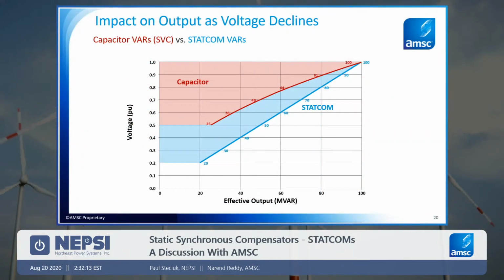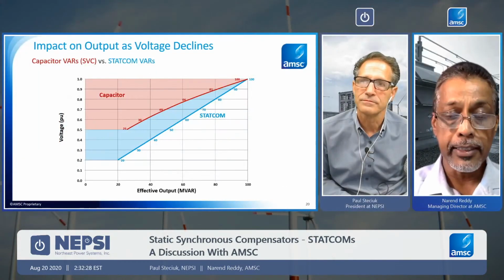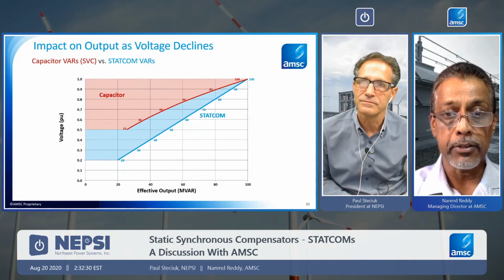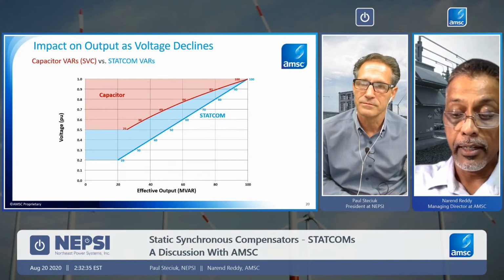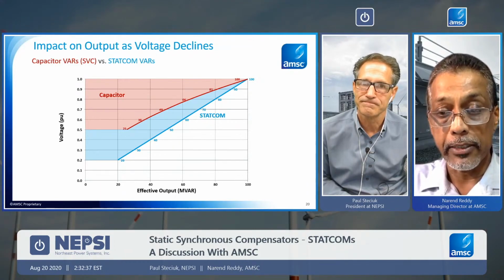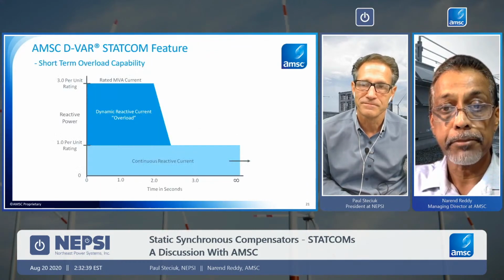What that means is that STATCOM technology can continue to operate, continue to generate current, as long as there is some voltage available on the grid to give it the reference for the frequency and the phase that it's looking for. Other than that, it will be able to provide all that current all the way up to 1 per unit voltage, incrementally better than a static capacitor bank.